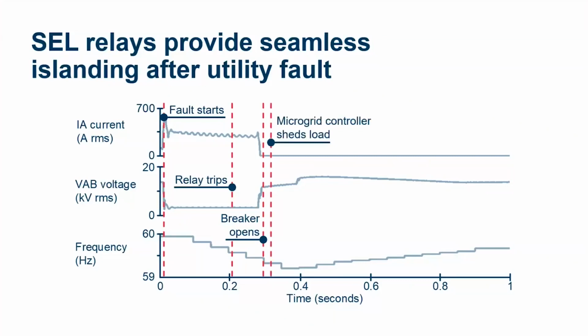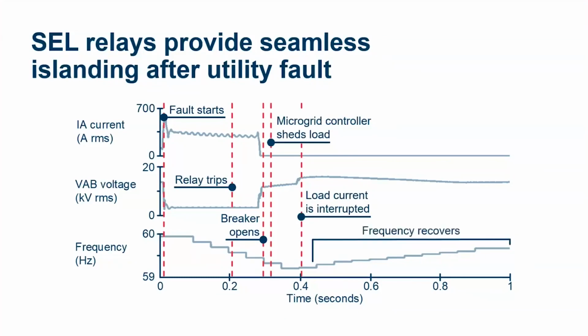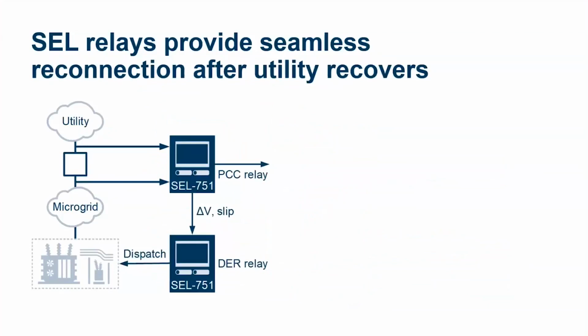Well, so we use a PowerMAX microgrid controller and a relay to shed loads throughout the power system, balancing. And this is the first point I made with that cycle of life. This is that separate, survive. This is resilient behavior done with an SEL protective relay. And the frequency recovers. Back on track, we never lost the power system. That's a happy customer.